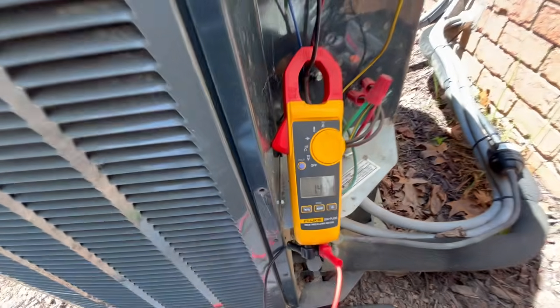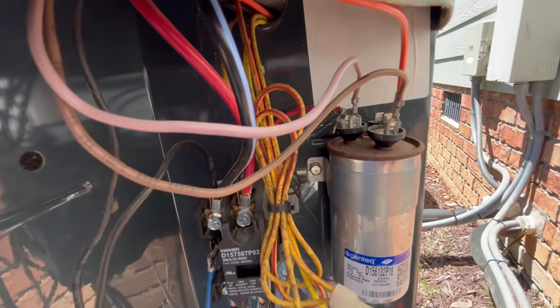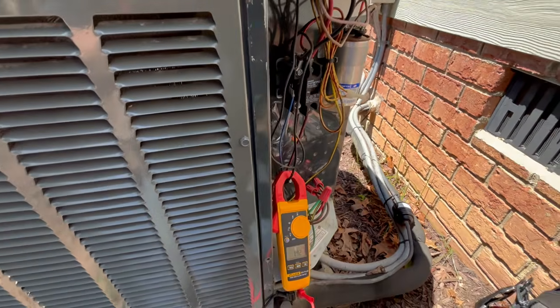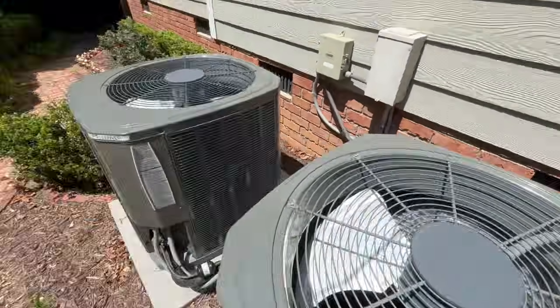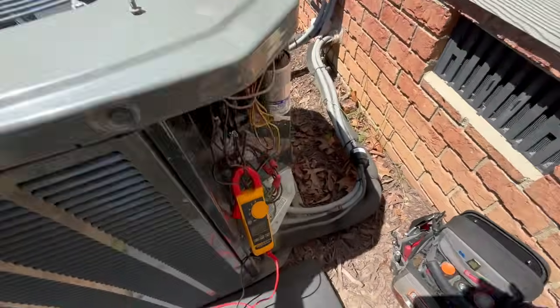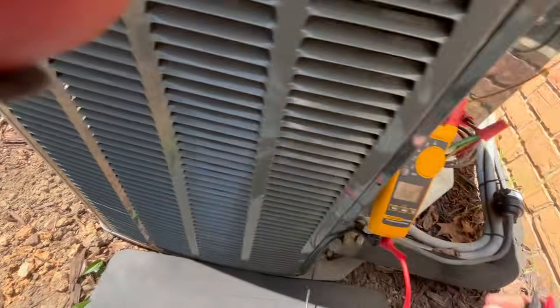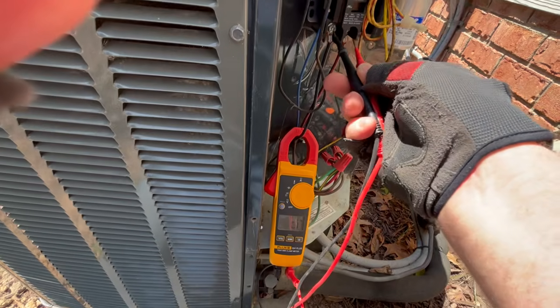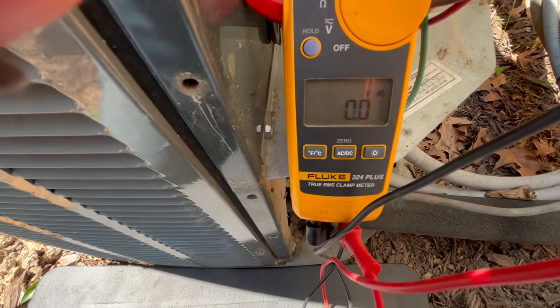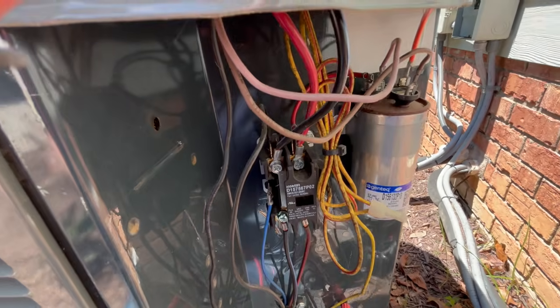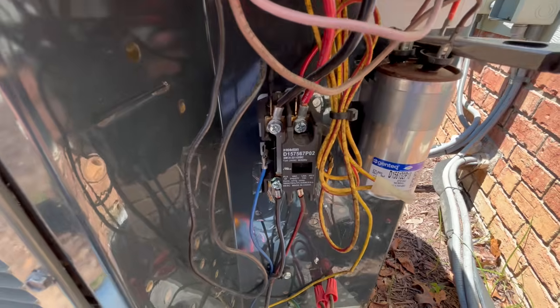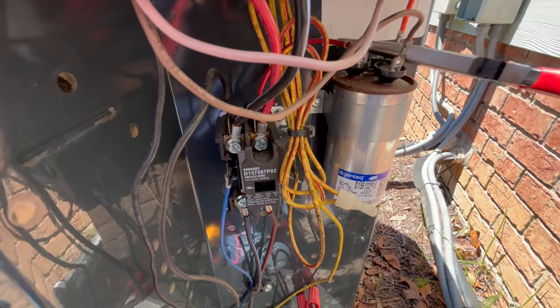Yeah, we spiked up to 81 amps trying to start. So luckily it's a nice easy call for a hot day. They're not all like that. Turn the breaker off. And the contactor is still pulled in. We will check voltage. 0. And take some needle nose. Like I said, I still like to discharge a capacitor even when it's blown before I go sticking stuff in there.